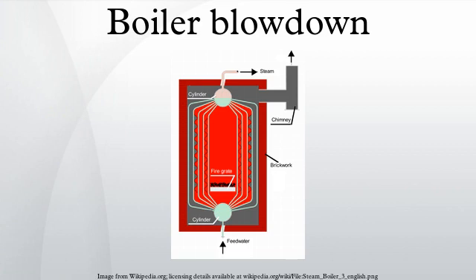Surface blowdown is normally fed to a flash tank and heat exchanger for heat recovery. The flashed steam can be used in the feed water heater. These energy economies are seldom practical with infrequent bottom blowdown. Surface blowdown offers the additional advantage of steady state operating conditions.